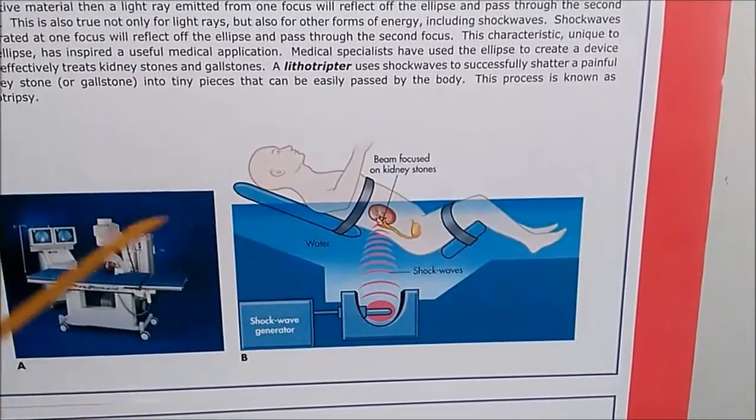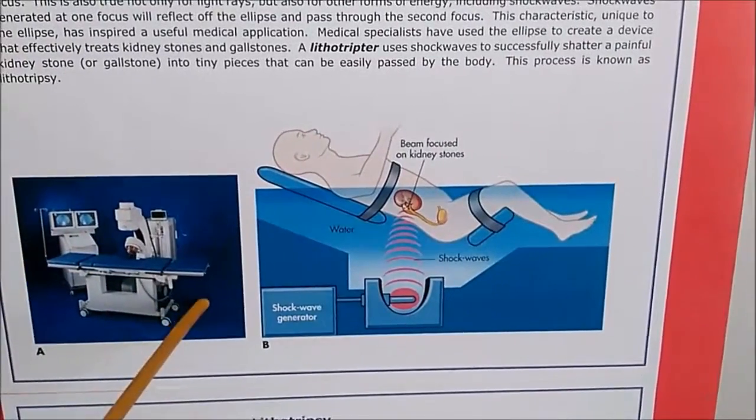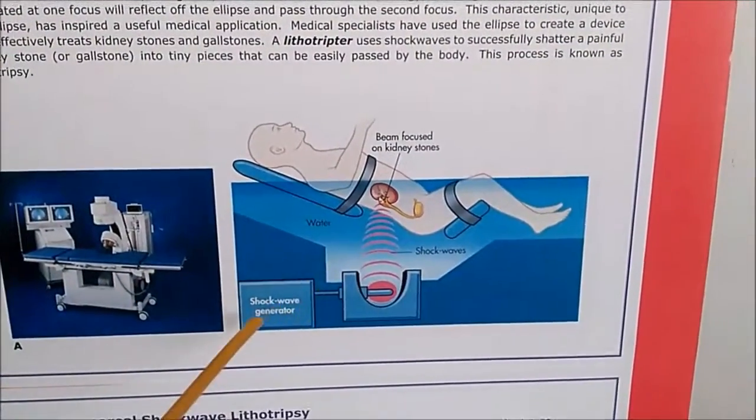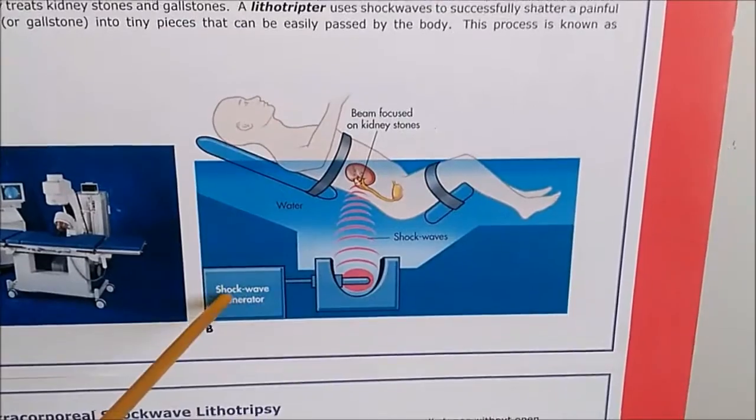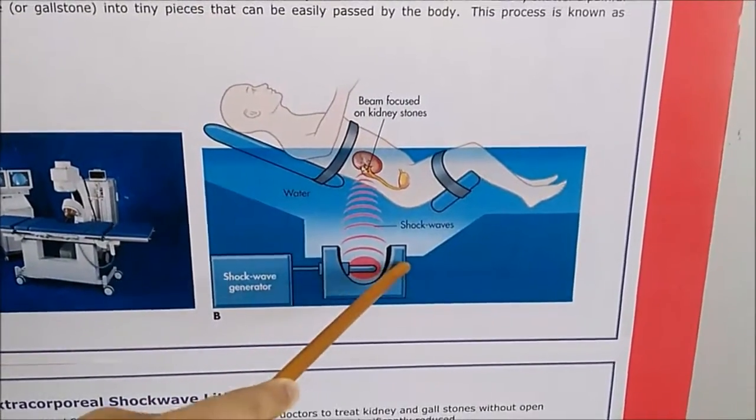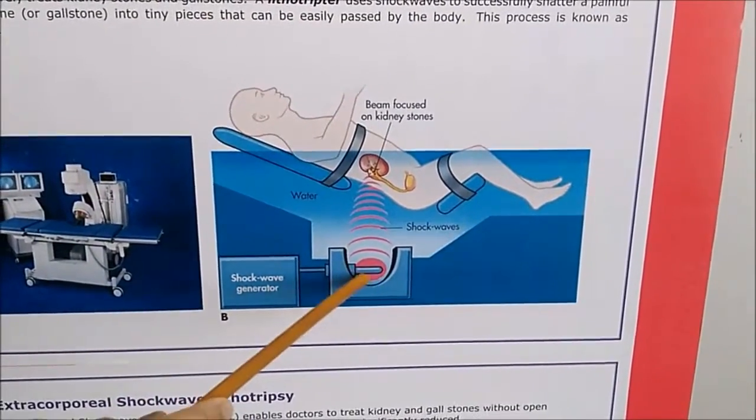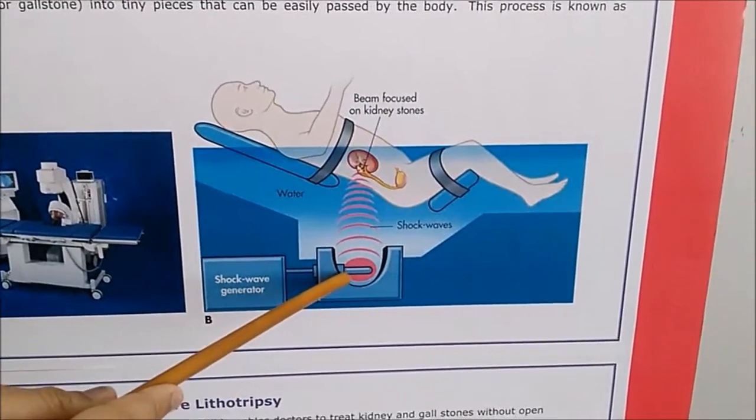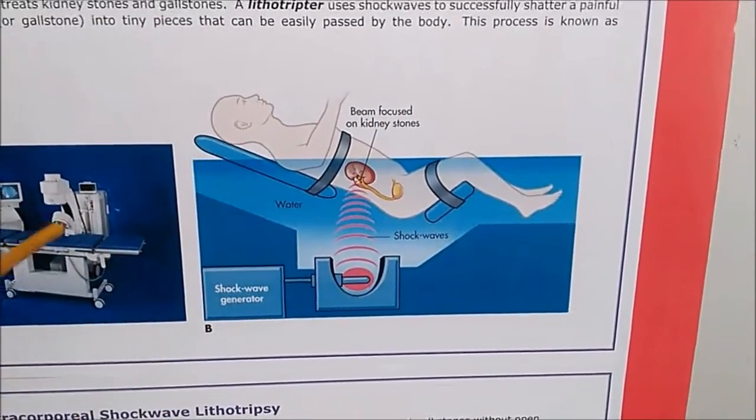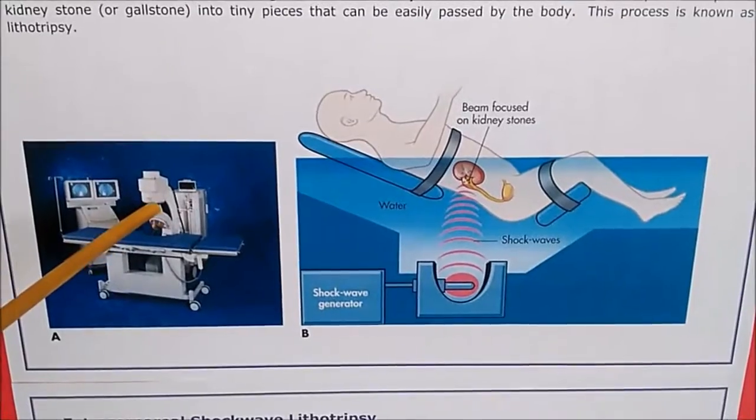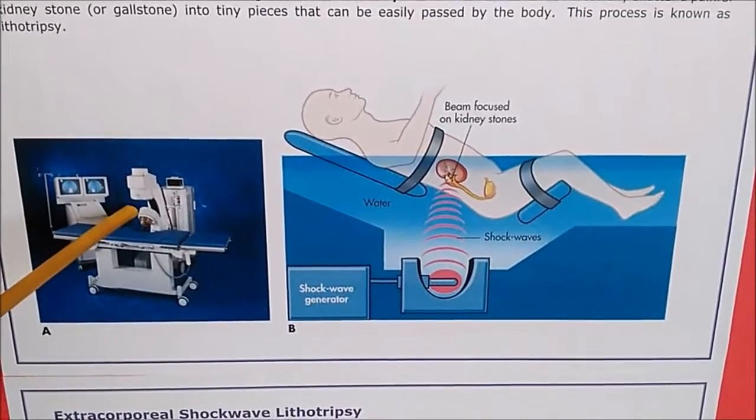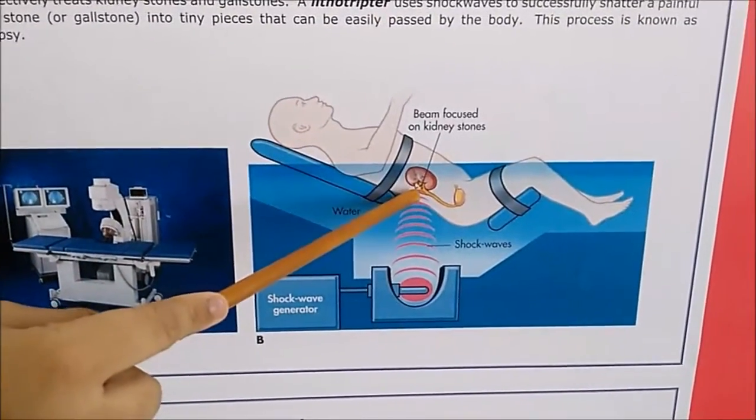The patient is put on a water cushion under the shock wave generator, which is a half ellipse. The shock wave generator generates shock waves. This right here is the x-ray. The x-ray locates where the kidney stone is.